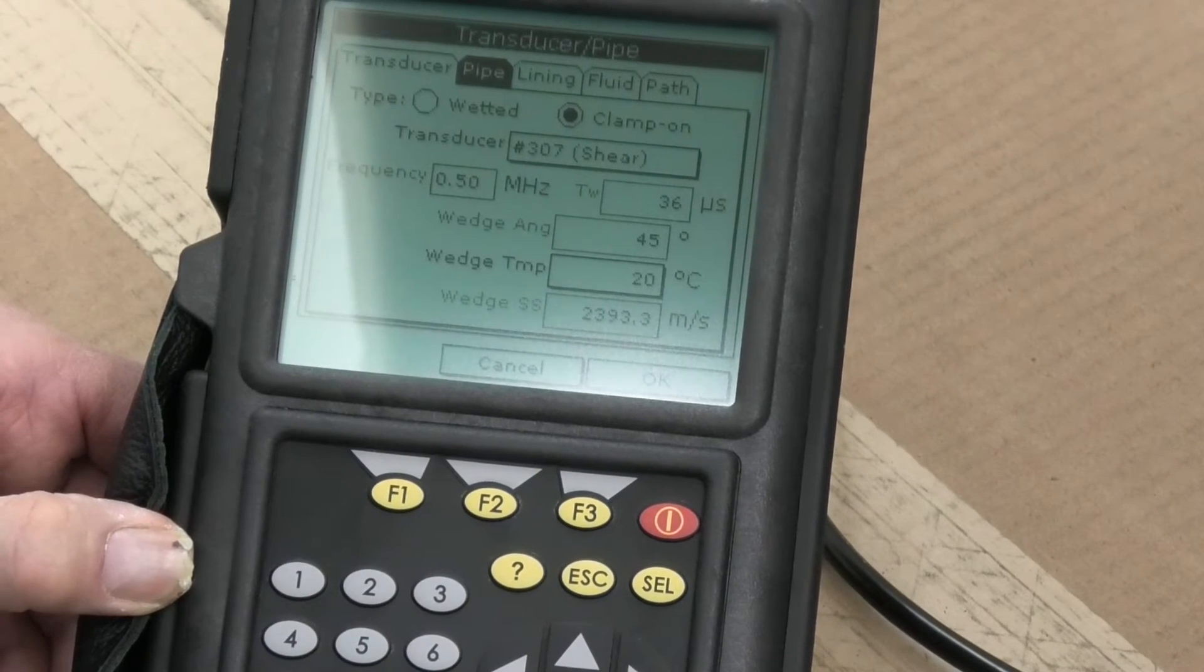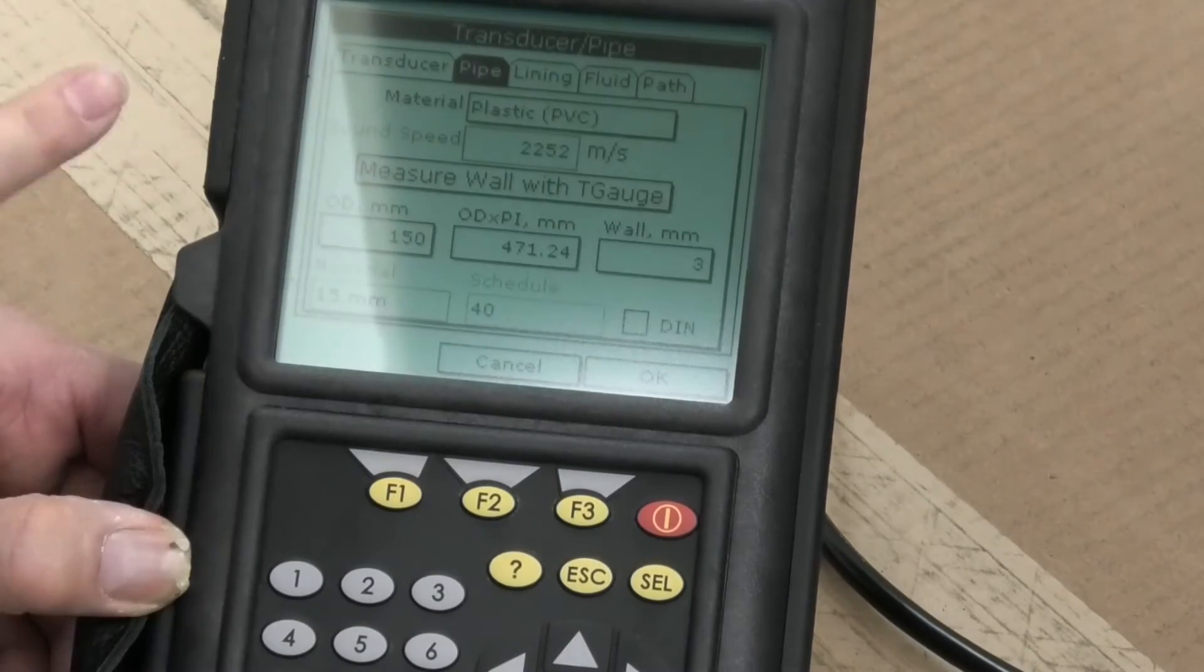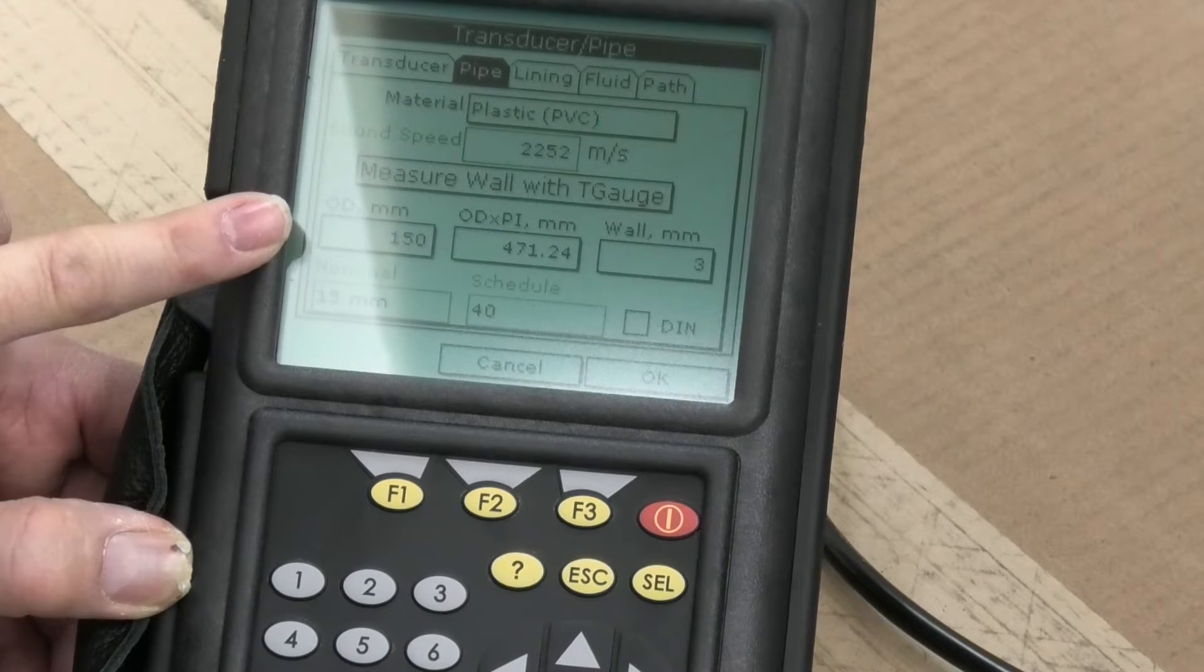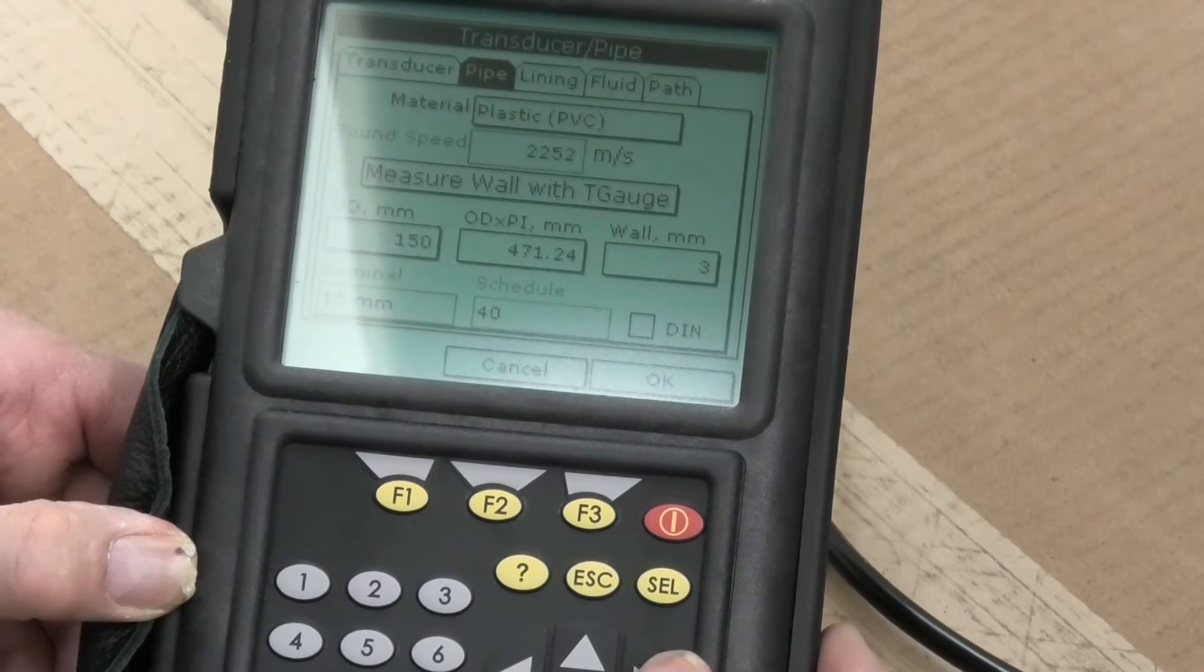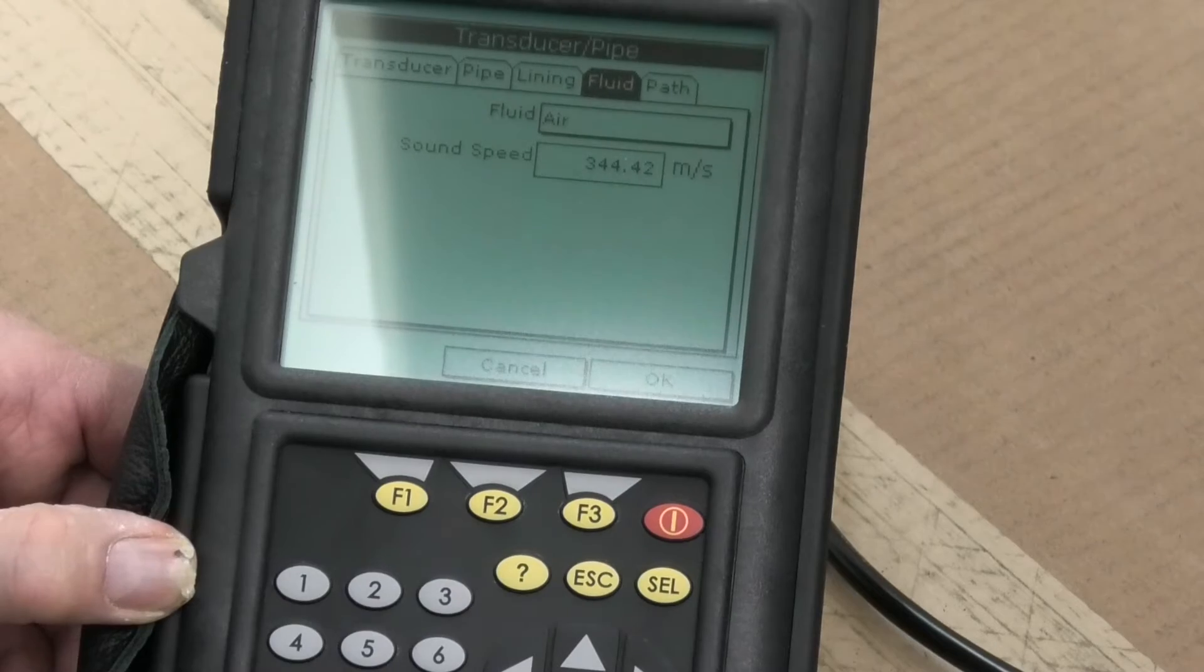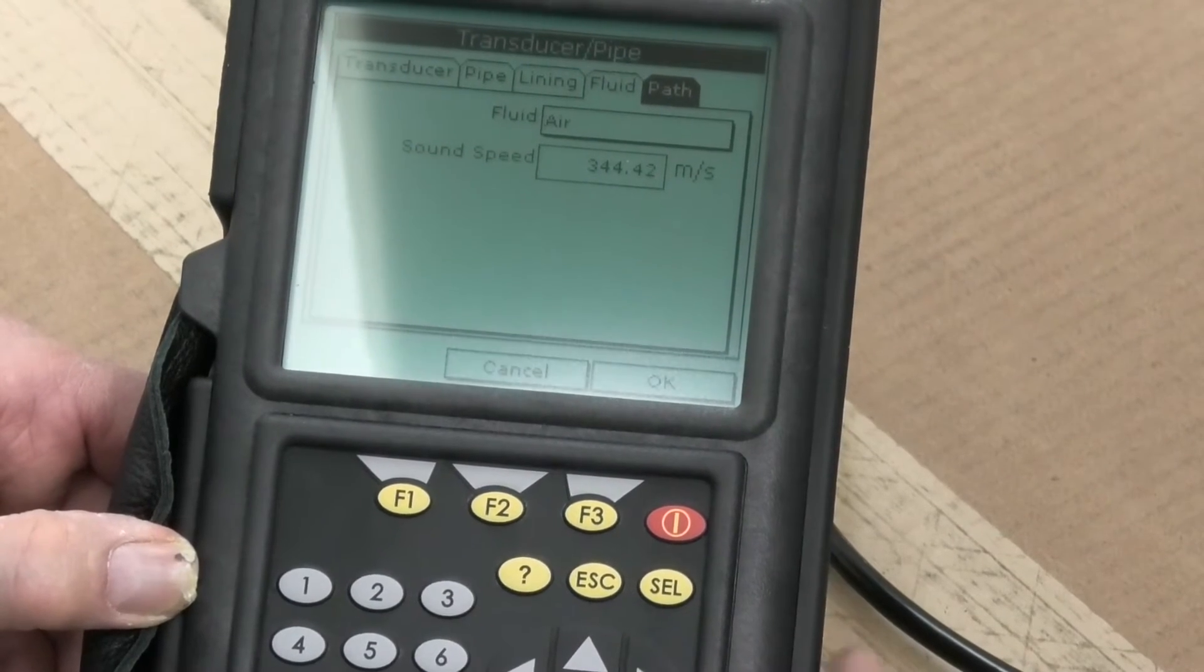In this case if I go enter on there for the pipe it will jump to that panel. Now I'm using a plastic pipe and we happen to know we've got the dimensions of this 150 by 3mm. It's not lined and the fluid we're putting through it is air, and the sound speed is 344.42 which is standard sound speed for air.